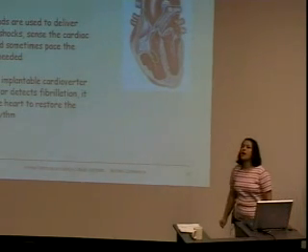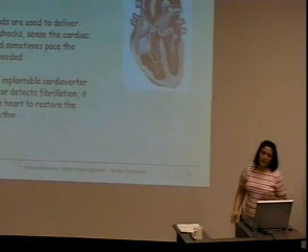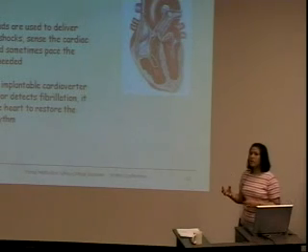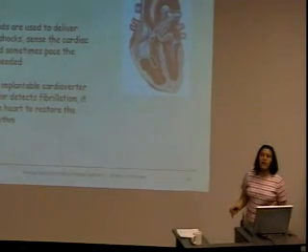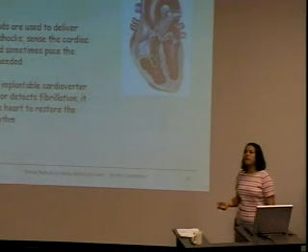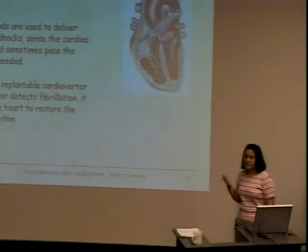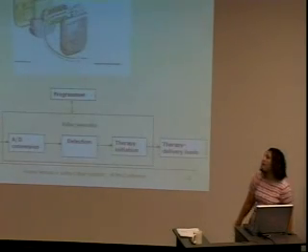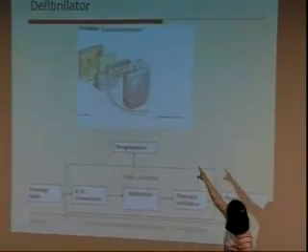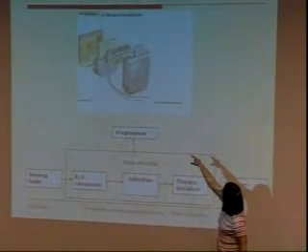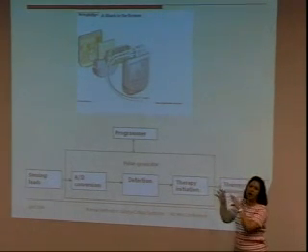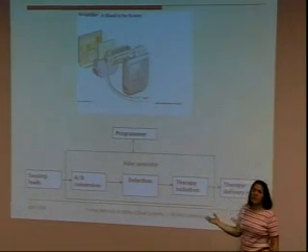The defibrillator is a shock delivering system which contains a battery, two sets of leads, an electronic part and a programmer part or a software part. The leads deliver shock in case the heart rhythm is not proper. So this is basically a defibrillator. At that part, you see the battery. At the middle part, this is the electronic part. These are the leads. And the programmer or the software part, which sits on a laptop or a small notepad computer, can be in the physician's office.